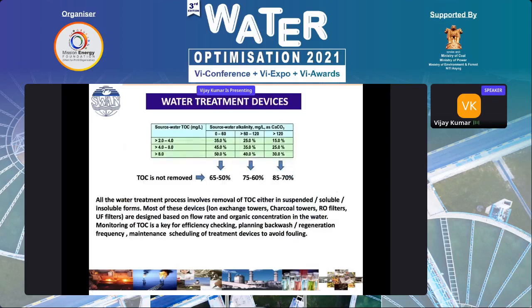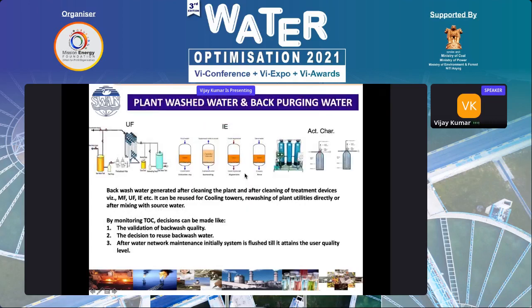So when we talk about water treatment, most TOC, in suspended, soluble and insoluble form, is to be removed by ion exchange towers, charcoal towers, and RO filters. UF filters are designed on flow rate and organic concentration. So TOC monitoring is useful for checking efficiency, and for planning backwash, regeneration frequency, and maintenance scheduling. If you don't measure, you definitely don't know how much is removed. There is a possibility that a lot of things cannot be removed, but by monitoring, you will come to know about it. So it's very important that you do this.